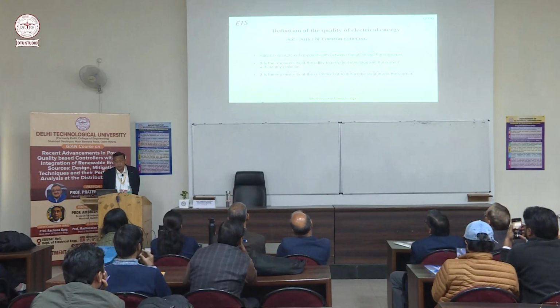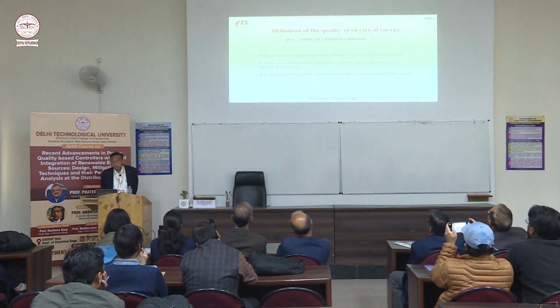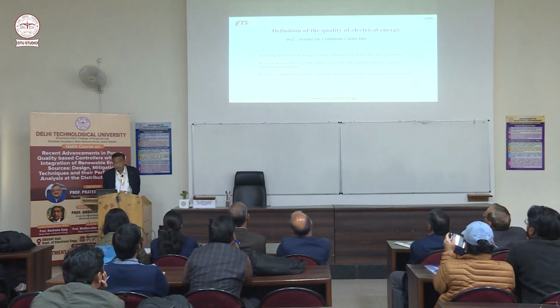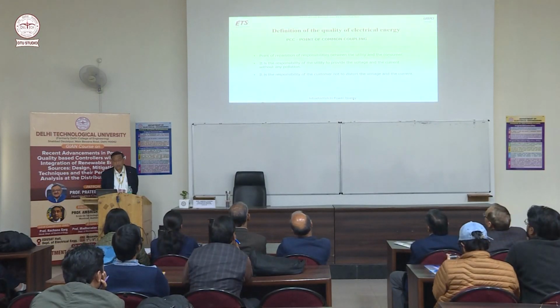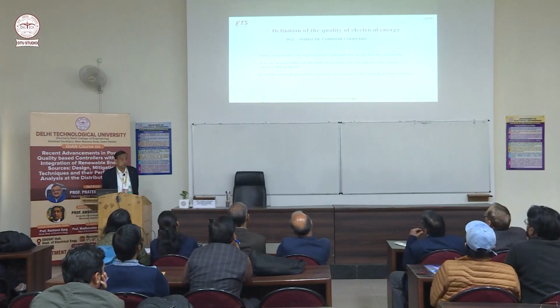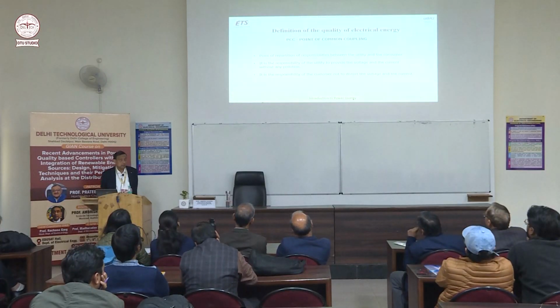So what is PCC? Point of common coupling. The point of repartition of responsibility between the utility and the customer. That is PCC, point of common coupling. It is the responsibility of the utility to provide the voltage without any pollution. The current is the responsibility of the customer, right? So it is the responsibility of the customer not to distort the voltage and the current.